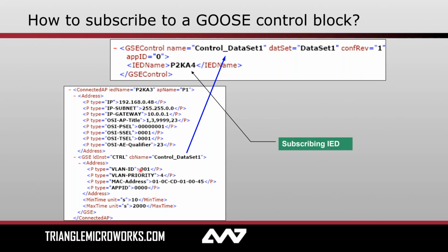This is where the VLAN ID is stored, the priority, the target destination MAC address, and then it also provides a reference to the GOOSE control block. The actual GOOSE control block itself is just referenced here. It exists down in the IED section, a little bit lower down in the file. And here's what a definition of a GOOSE control block would look like. So you've got the name, you've got the data set, and then crucially, you've got the IED name of any potential subscribers. So ultimately, this is where the subscription is configured.